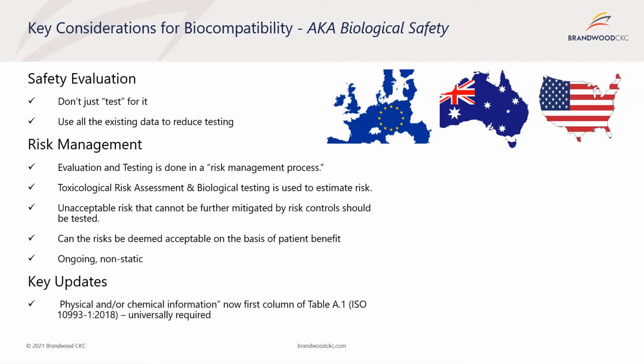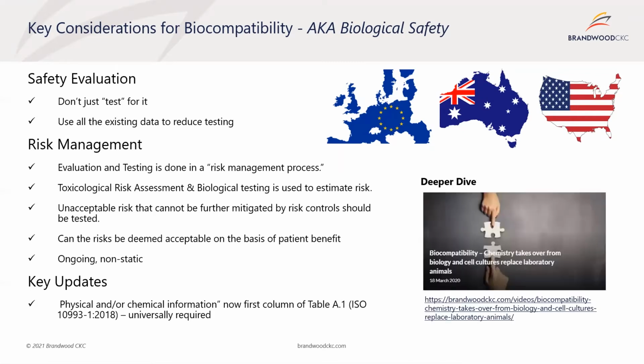One important consideration is that physical and/or chemical information is now the first column of Table A1 in the ISO 10993 2018. So this is basically universally required. Doesn't mean that all the testing has to be conducted, but that qualification of the physical and chemical characterization really needs to be addressed for all products. Again, a deeper dive: we've recently this year also provided a webinar. So here's a link if you wanted to jump more in detail into it.